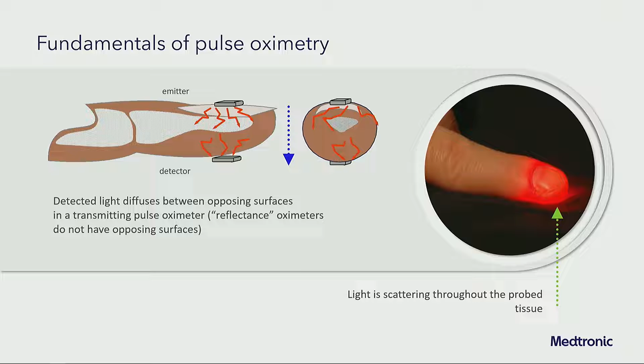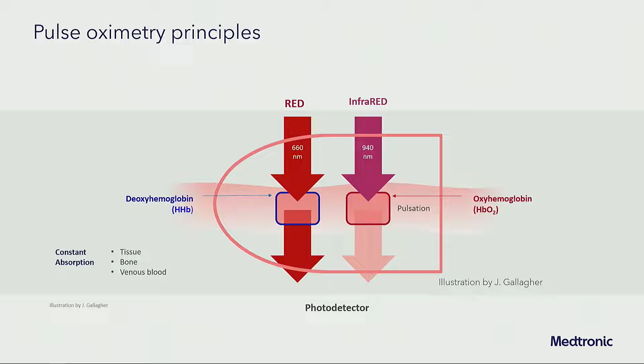You may also remember that that pulse oximeter is transmitting two different wavelengths of light. There's red light at 660 nanometers and infrared at 940 nanometers. And the reason that it's transmitting two different wavelengths of light is that that light is absorbed differently by oxy and deoxyhemoglobin. And so you're taking advantage of the different absorption curves of those two forms of hemoglobin to tell you what the oxygen saturation is.